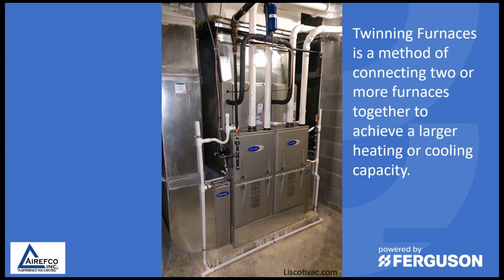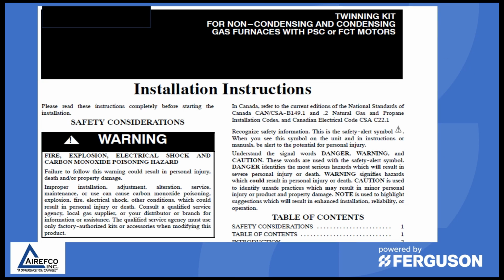Twinning furnaces is a method of connecting two or more furnaces together to achieve a larger heating or cooling capacity. In tech support, we get many questions about twinning furnaces, and we reply that there are kits available to twin furnaces. You'll notice that this installation instruction covers non-condensing furnaces and condensing gas furnaces with PSC motors or FCT, which are ECM motors. So there's a wide variety of different ways and different models of furnaces that you can twin if it fits your application.